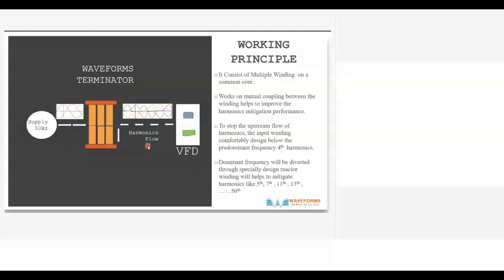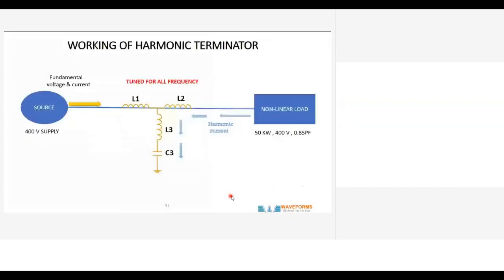So the dominant frequency will be diverted through a specially designed reactor. Besides using mutual inductance and phase shifting to mitigate harmonics, they use a tuned type of filter also. It's basically a broadband filter, which will filter a wide spectrum of harmonics. The dominant frequency will be diverted to a specially designed reactor winding, which helps to mitigate the 5th, 7th, 11th, 13th, and 15th.